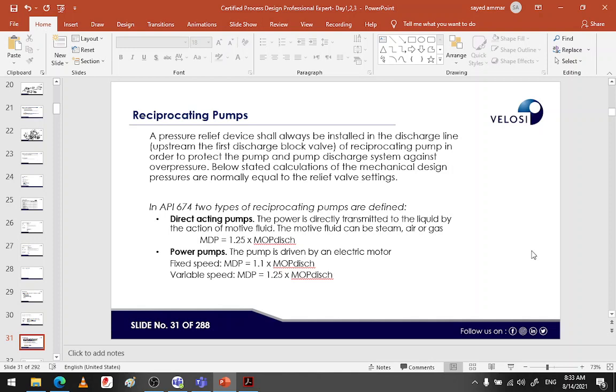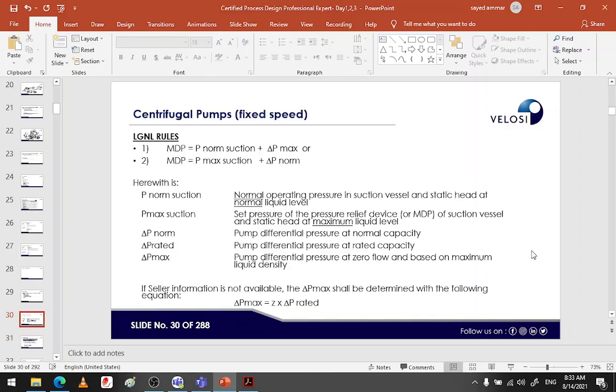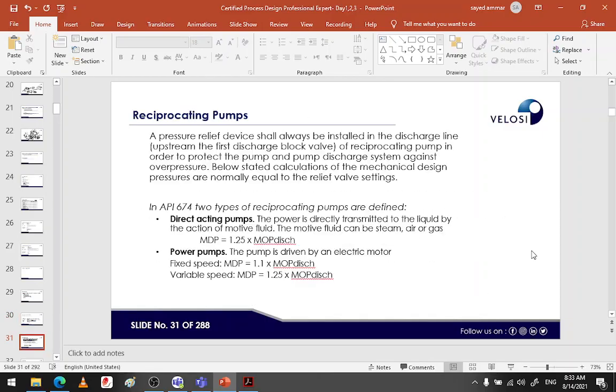Reciprocating pumps. Is it different from centrifugal pumps? Yes. Can we have a shutoff pressure for this pump? Yes. Are we going to protect these pumps? Yes. There is a saying among mechanical engineers that you shouldn't be afraid of the mechanical reciprocating pump. You should just be afraid of the piping downstream of this pump.